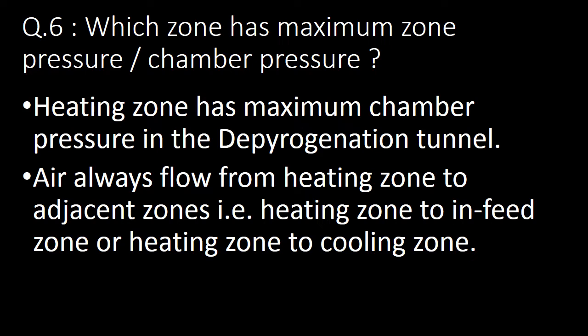Sixth question: which zone has maximum zone pressure or chamber pressure? The heating zone has maximum chamber pressure in the depyrogenation tunnel. Air always flows from the heating zone to adjacent zones, i.e. heating zone to inlet zone or heating zone to cooling zone.